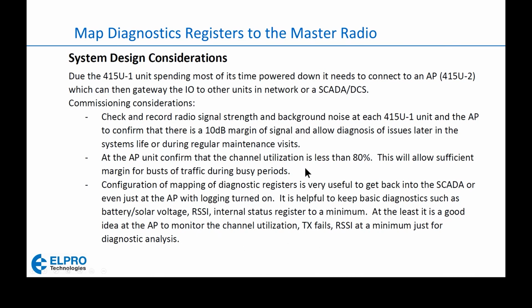One of the things that we have in our radios is we look at channel utilization to figure out how busy the radio network is. And that helps us diagnose any problems we might be having with the radio system. Like, do we need to add IP filtering at the SCADA host? Is a whole bunch of unnecessary radio traffic causing the channel to be utilized much, much higher than normal? So all kinds of diagnostic data is available, and you can store that all on the master radio in your control room at your SCADA master location, so that you can have a great idea as to what's happening with the remote units.